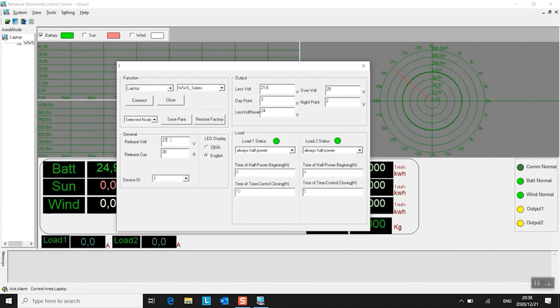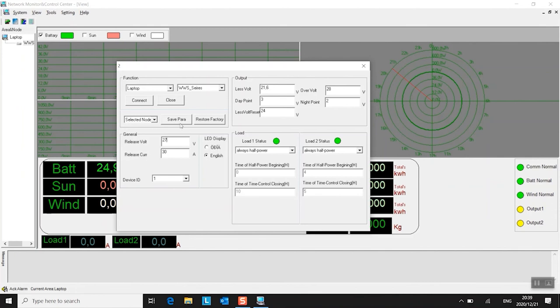You would change the release voltage here on the turbine if you were connecting to lead acid or to lithium. So it depends on the battery types you've got. So on the lead acid battery system, float voltage would be about 27 volts. Put it on like that. So save parameter.